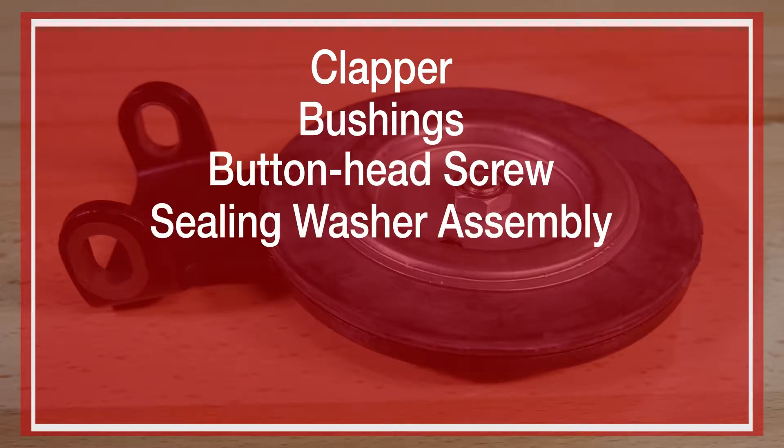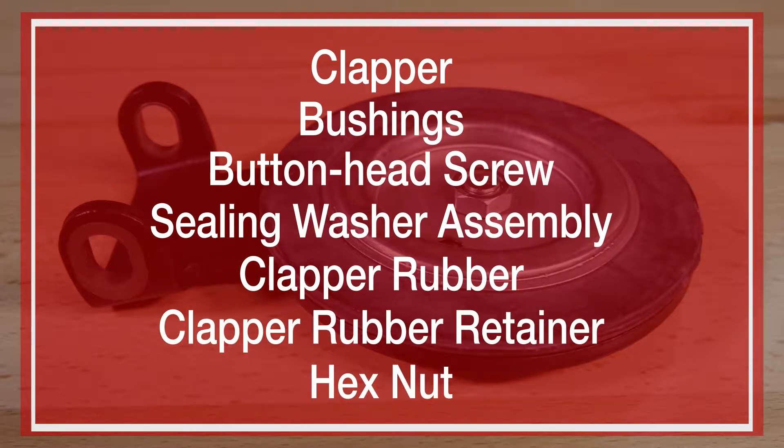We will be covering the replacement of the clapper assembly which consists of the clapper, the bushings, the button head screw, sealing washer assembly, clapper rubber, clapper rubber retainer, and the hex nut.